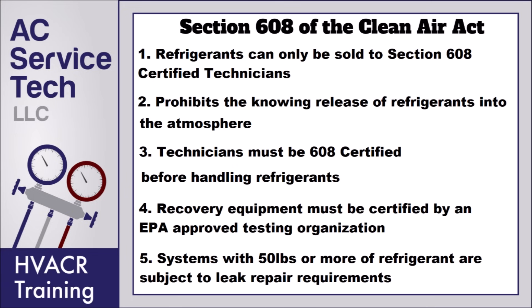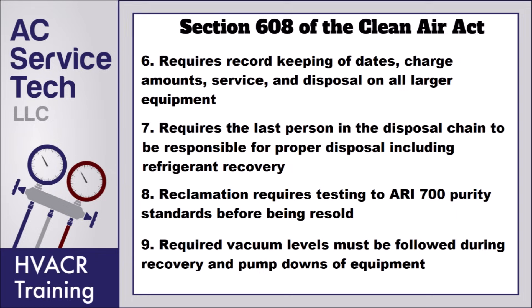In section 608 of the Clean Air Act, refrigerants can only be sold to technicians that are EPA 608 certified. It also prohibits the knowing release of refrigerants into the atmosphere. Technicians must be 608 certified before handling refrigerants. Recovery equipment must be certified by an EPA approved testing organization. Systems with 50 pounds or more of refrigerant are subject to leak repair requirements. It requires record keeping of dates, charge amounts, service, and disposal on larger equipment. It requires the last person in the disposal chain to be responsible for proper disposal including refrigerant recovery. Reclamation requires testing to ARI 700 purity standards before being resold, and required vacuum levels must be followed during recovery and pump downs on equipment.